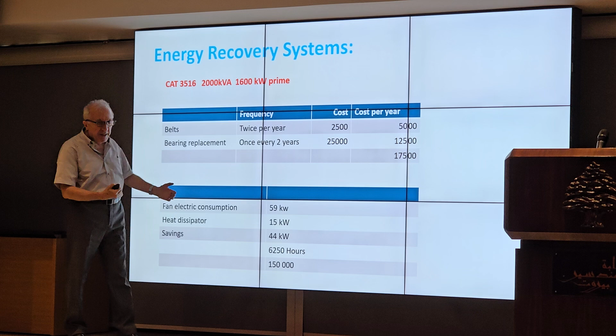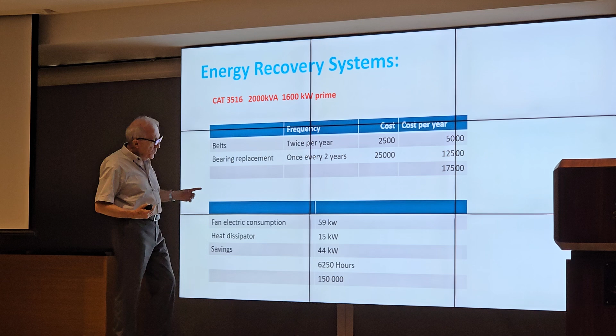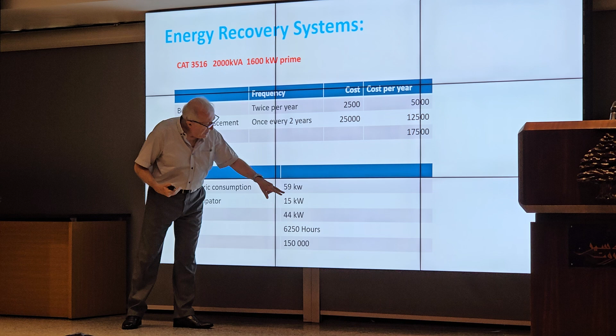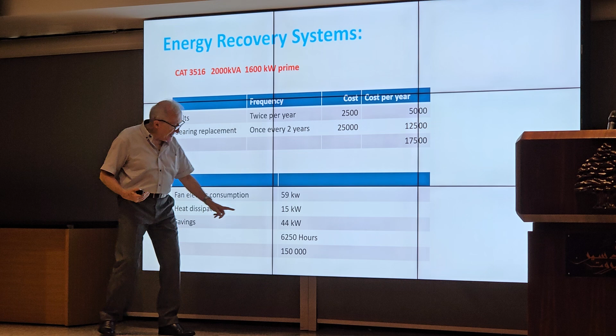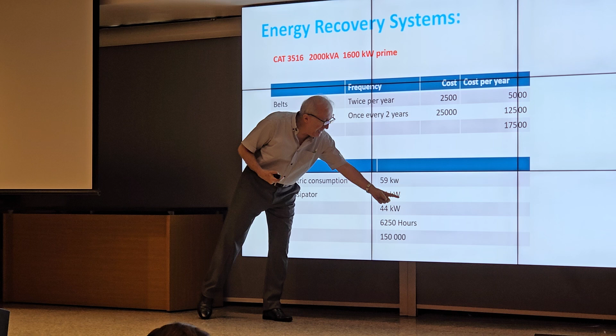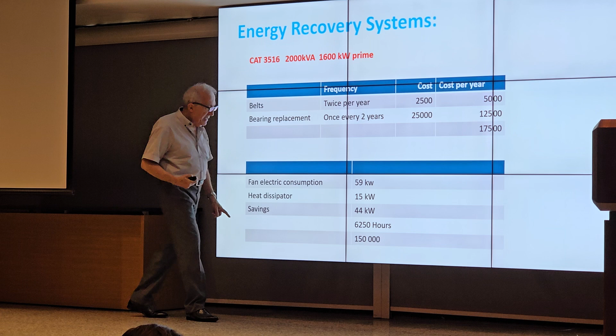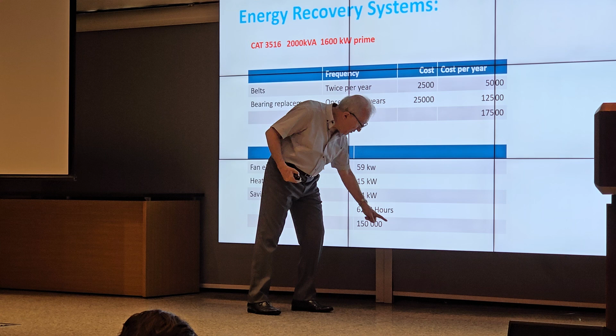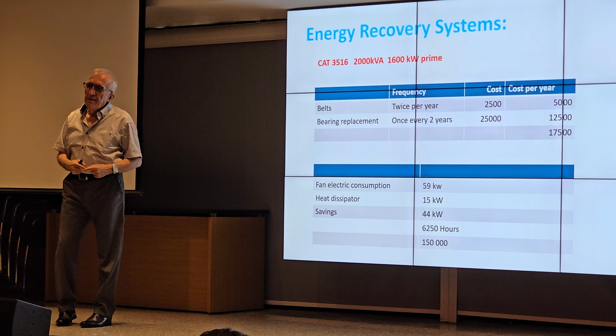And we put in, because we are now cooling the generators not by the radiator, but by getting this heat in the recovery. We should consider that we are saving 59 kilowatts, but we put 15 kilowatts as a heat dissipator, because sometimes they don't use our heat fully, so we have a backup dissipator. So we are in fact saving 44 kilowatt hours, and for 6,250 hours, this makes $150,000 saving only from the radiator fan.